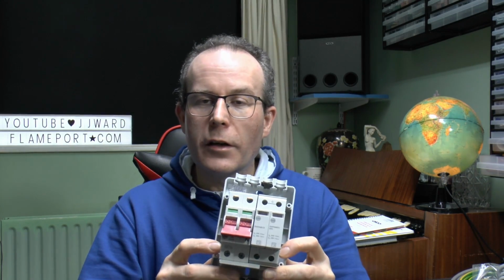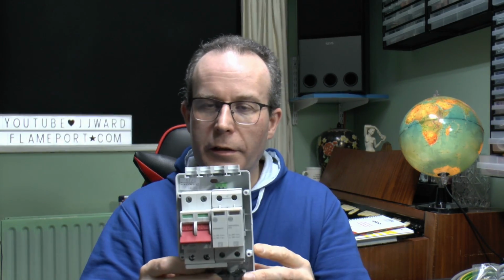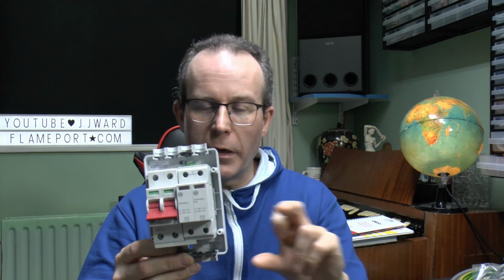What you don't want to do is to have your main switch or consumer unit or whatever here, and then put this surge protector device over here in a separate thing and just have 3 wires going over to it, line, neutral and earth, because that is the critical distance, and by putting it over there on its own you've extended that massively, and even at that sort of distance that's half a meter gone already. 25 centimeters there, 25 centimeters coming back, that's your half a meter, so you want to definitely avoid that. So separate enclosure. Make sure the wires come in and go out as well, or in the consumer unit, obviously, same deal. You do not want a separate box with only the 3 conductors to it, because that's going to be way over the half a metre, in many cases way over the metre as well.